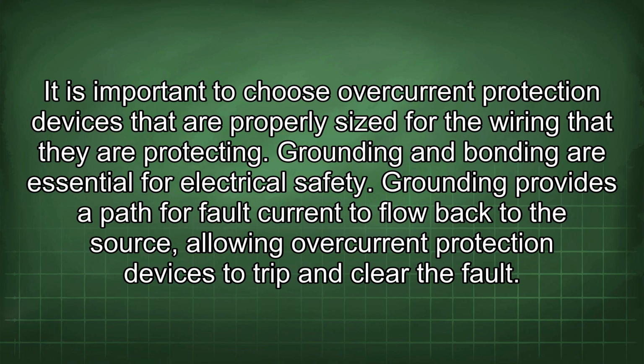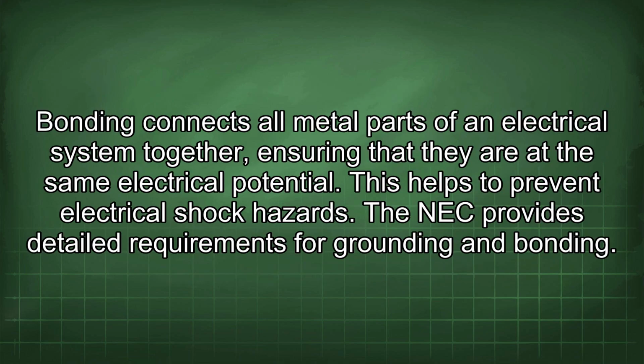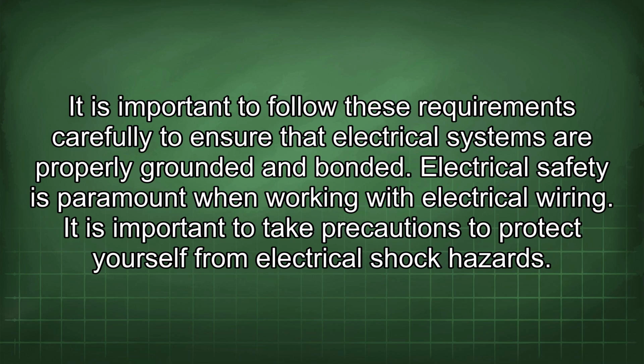Grounding and bonding are essential for electrical safety. Grounding provides a path for fault current to flow back to the source, allowing overcurrent protection devices to trip and clear the faults. Bonding connects all metal parts of an electrical system together, ensuring that they are at the same electrical potential. This helps to prevent electrical shock hazards. The NEC provides detailed requirements for grounding and bonding. It is important to follow these requirements carefully to ensure that electrical systems are properly grounded and bonded.